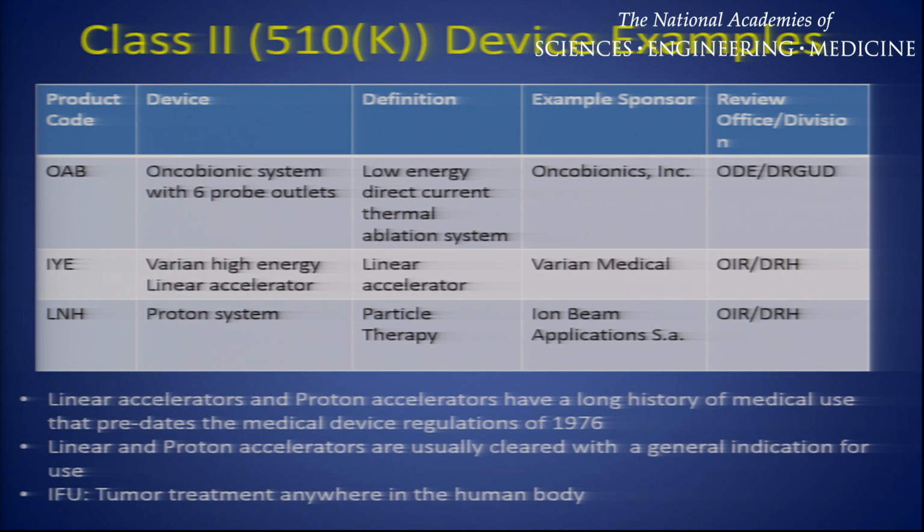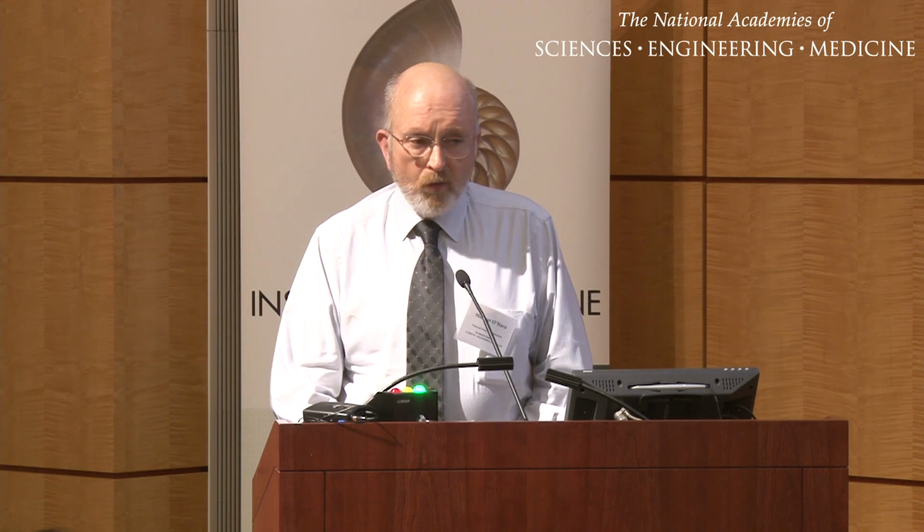Linear accelerators and proton accelerators have a long history of medical use that predates the medical device regulations of 1976. Linear accelerators and proton accelerators are usually cleared with a general indication for use. What that means is that they can be used for cancer treatment anywhere in the human body. So if a sponsor comes in and calls out a specific application, FDA then gets real interested in what that indication is, what their clinical evidence is. And in some cases, we give the sponsor a hard time when we see their marketing material and what they're actually marketing. So the general tool claim that you can use a linear accelerator or a proton accelerator to give a dose of radiation therapy is how they're cleared.